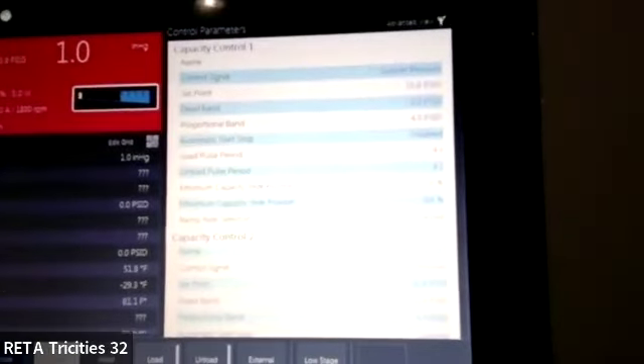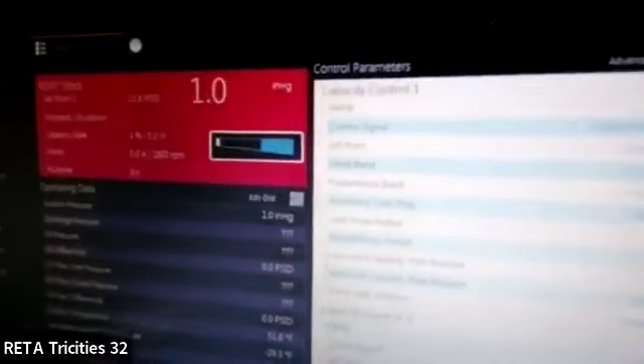So this would be something like if you guys had a pump down mode, or were in shutdown and you wanted to change the suction pressure, so that you're not in the vacuum anymore and you want to run cold storage and you're only at 7 pounds or something. You could have control 1 or control 2, and all you've got to do is select that. The other part of this is you can actually tell the machine to auto start and stop based off of suction pressure.